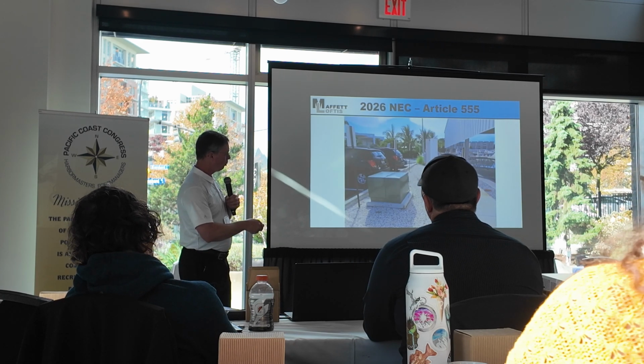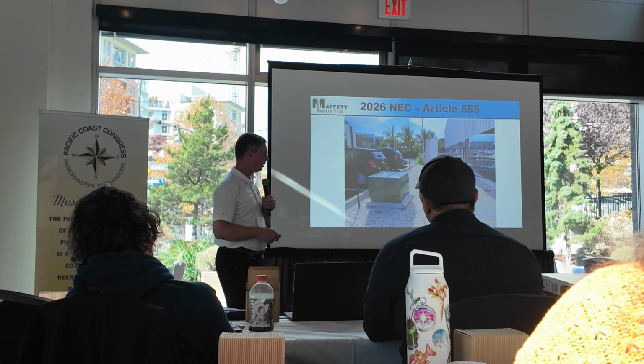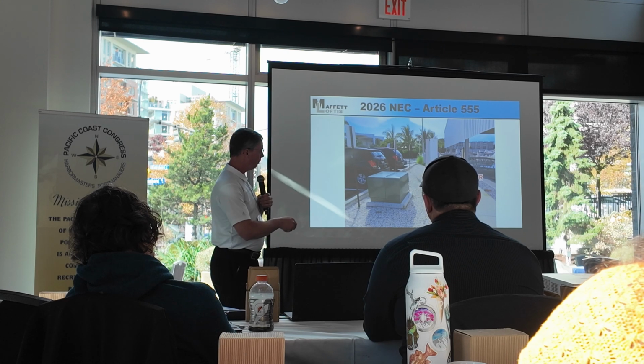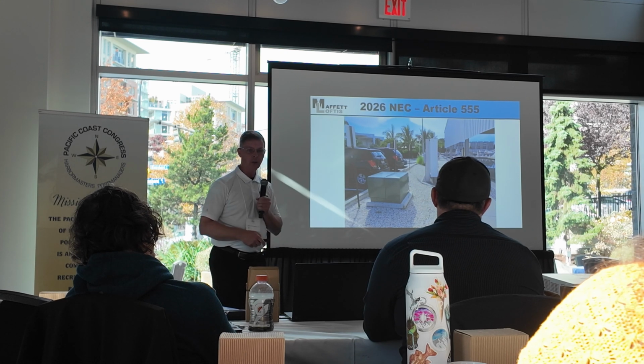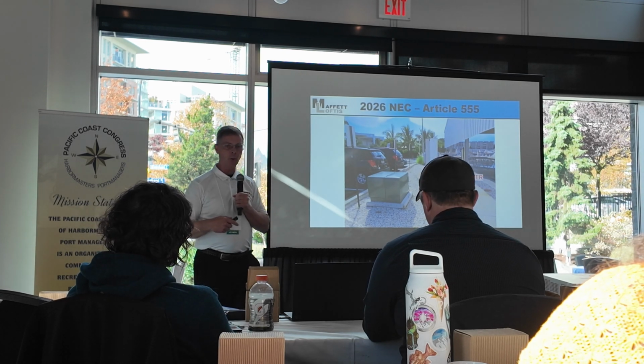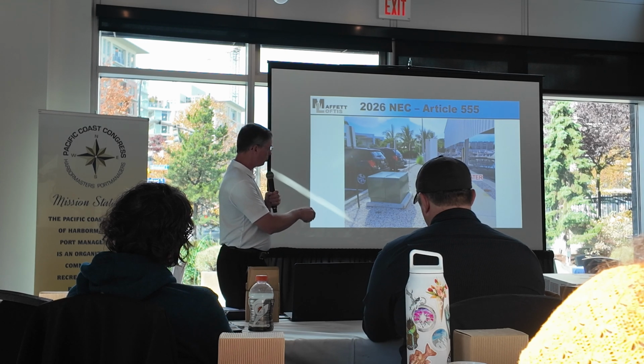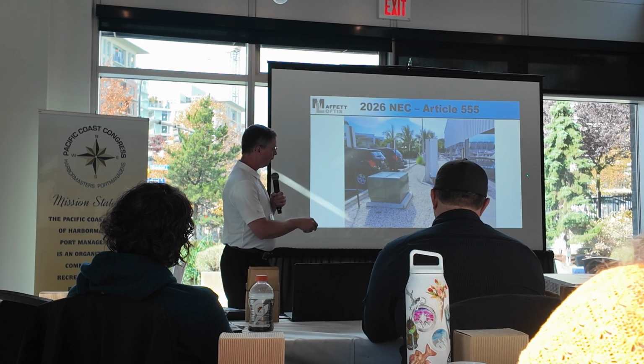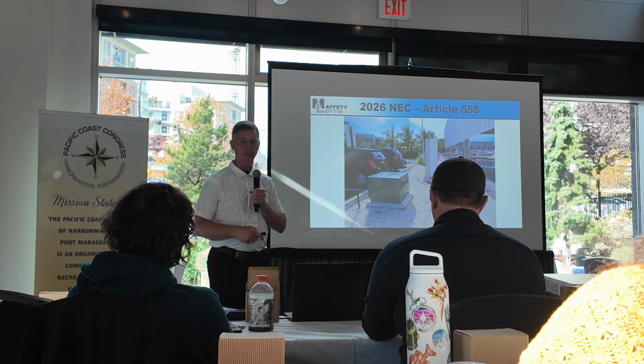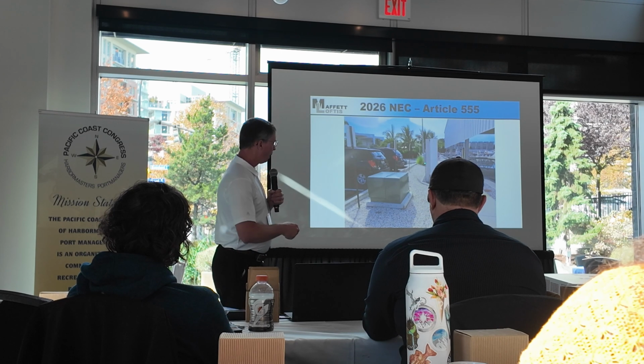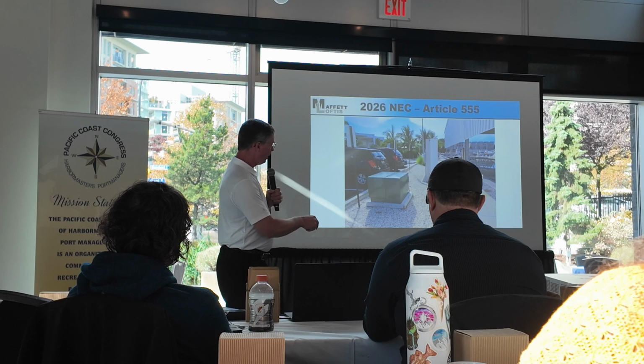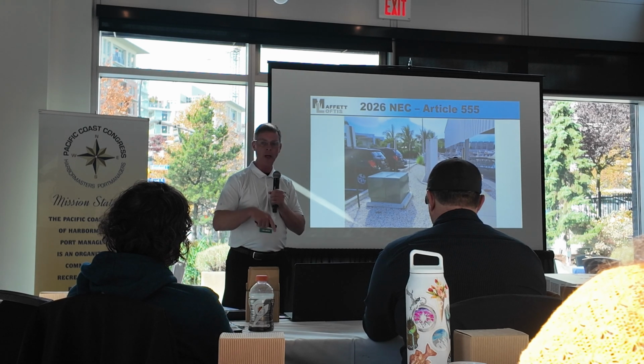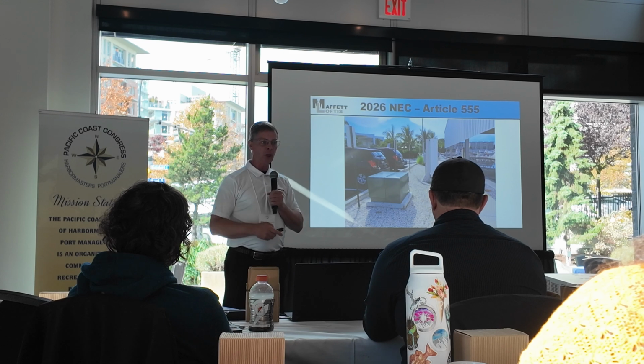And for example, here's a project down in St. Pete, and it's about 9 feet from the water's edge. In this case, that piece of service equipment right there is the utility transformer, and that is the service equipment. There's the meter. It's within 10 feet of the water, so we'd have to create an equal potential plane around there. What that means is that the metal structure here and even the ground that you stand on has to be equal potential within 3 feet all the way around this equipment.